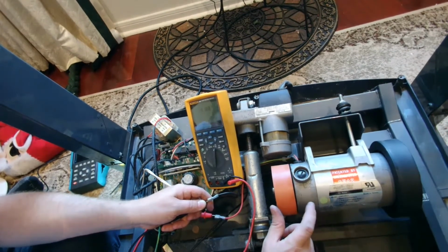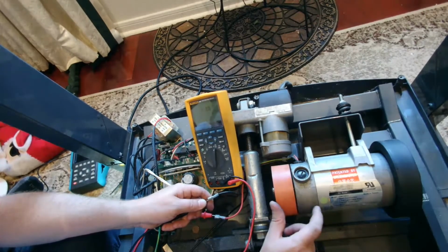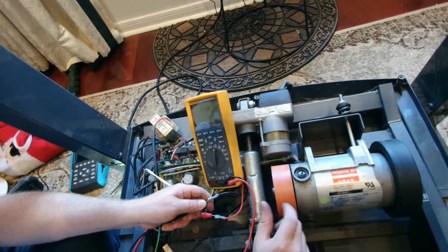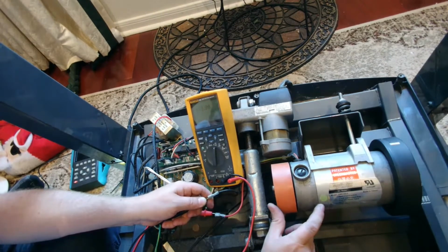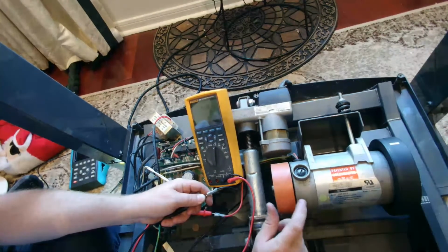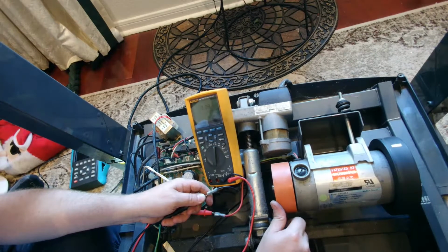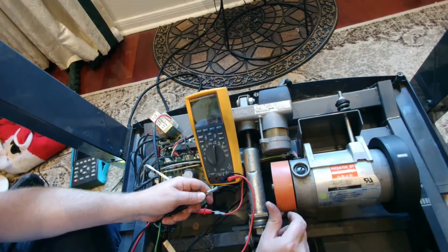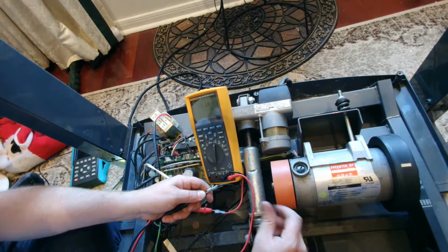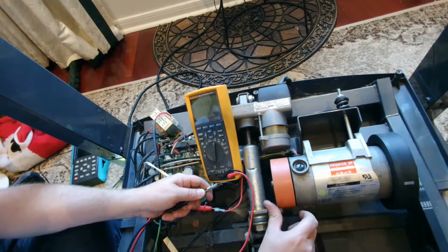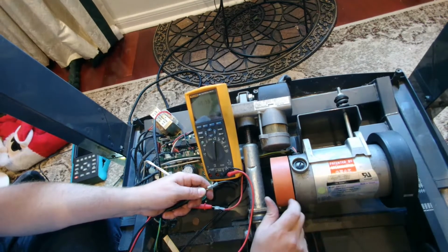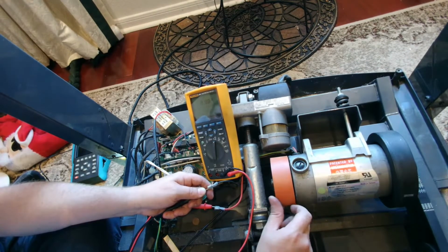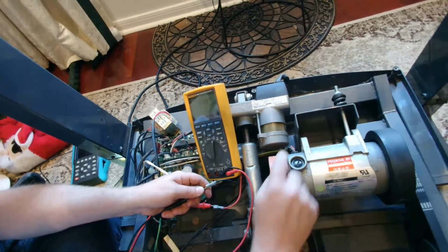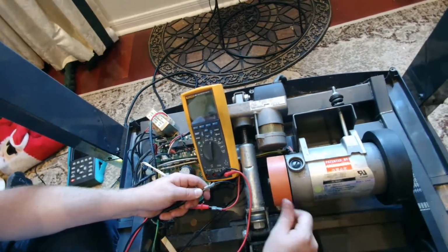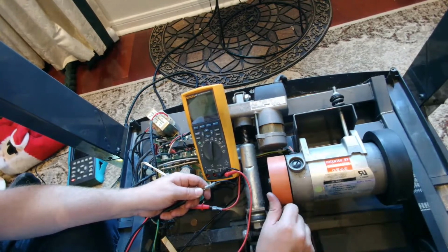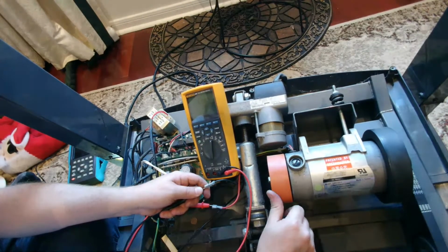You could technically do this if you got dead spots, even if you didn't have access to your commutator bars to take a look at them physically. You could do this exact same process: just hook your meter up to the wires coming out of your coils and then rotate it. If you got any dead spots, you'll see it go really high, and when I stop moving, it goes down to 1. You'll see it be like 100 or 200 ohms, or even a kilo ohm, and that's going to show you that your commutator bars in that particular region are damaged, or your coil's damaged. This looks good.